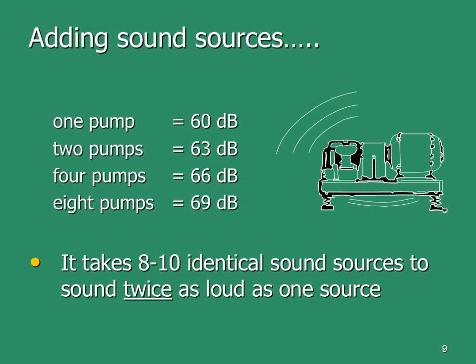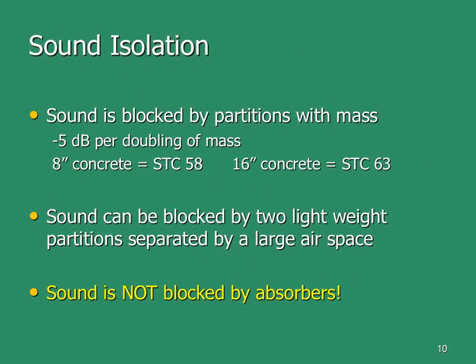If you double the amount of energy, it only adds 3 decibels. So if you have one pump making 60 decibels and add an identical second pump, the level will be 63. If you go from 2 to 4, you go up to 66. From 4 to 8, you'll reach 69. It takes roughly 8 to 10 decibels to be twice as loud as the previous level - that's twice as loud to your ear, but 10 times the vocal effort for me.